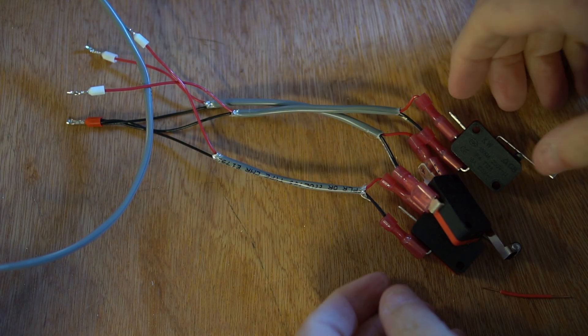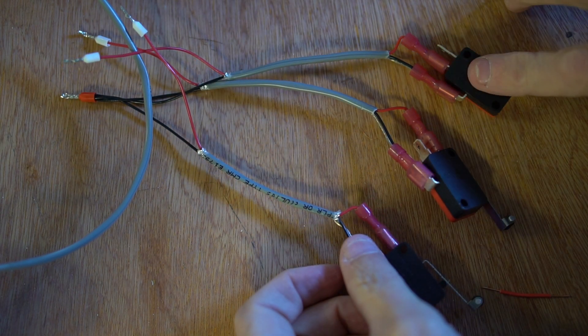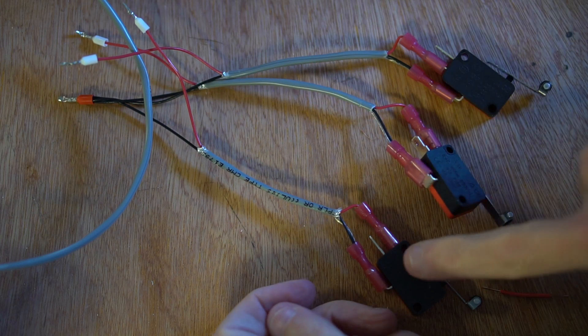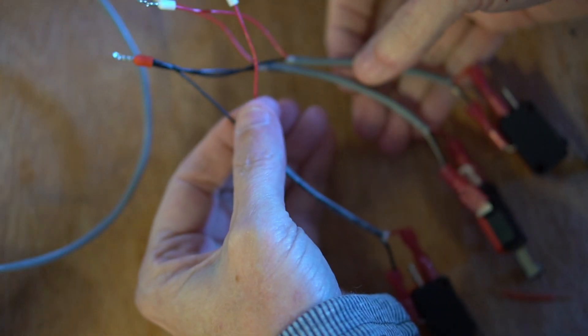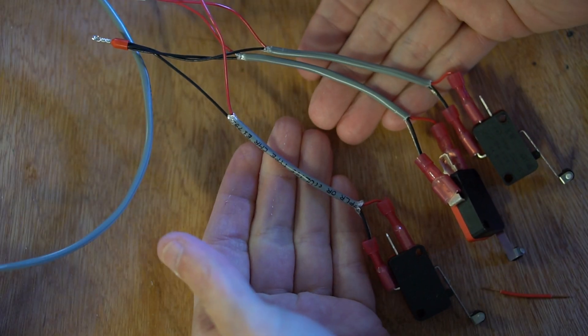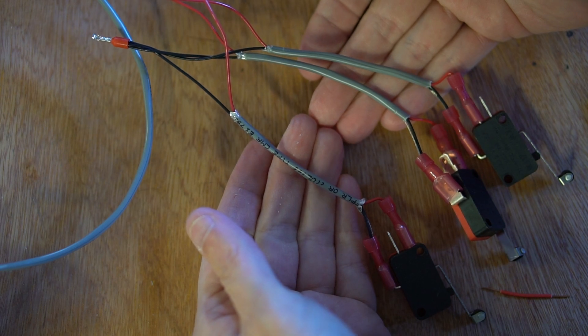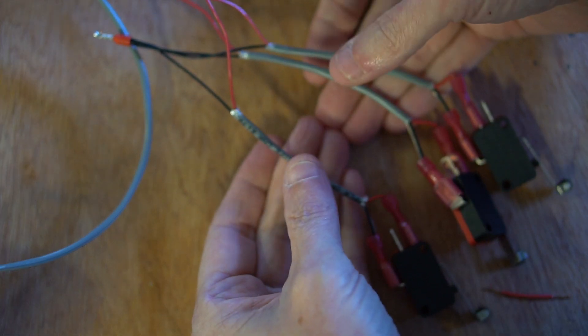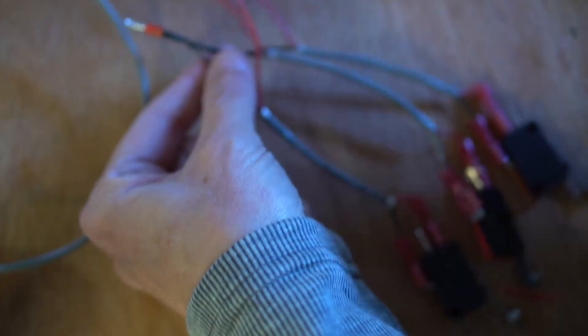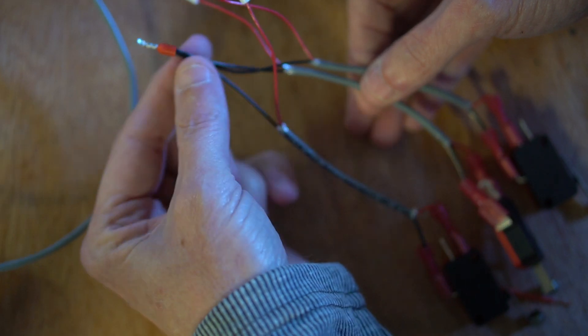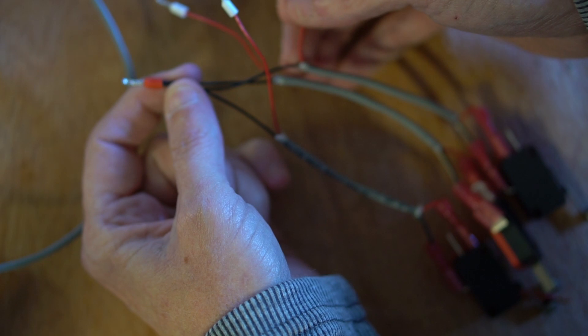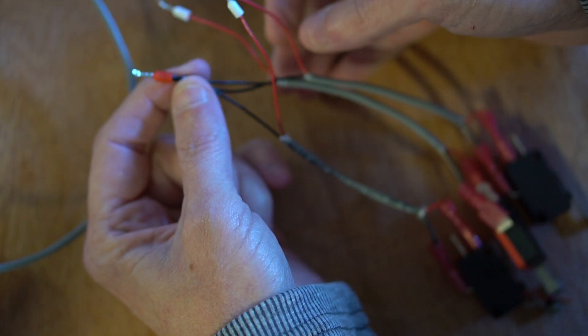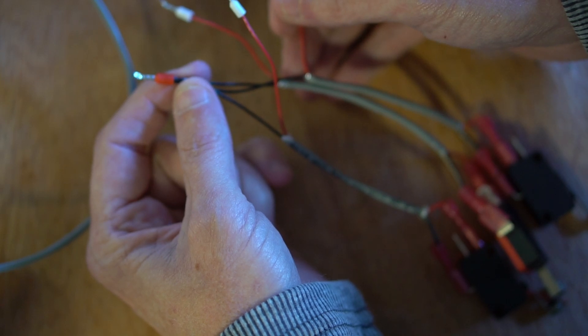I'm going to demonstrate connecting three limit switches. One for the home, one for the plus-plus, and one for the minus-minus. I'm using shielded cable, and there are two conductors in each cable. I'm using really short cables just for demonstration purposes. Of course, you'll want to use shielded cable because these are really susceptible to noise. And enough noise can stop the machine. I connected all the black conductors together along with the shield conductor, since these will be going to the ground terminal. I'm using wire ferrules to terminate the ends of these wires. I put a link in the description where you can get these wire ferrules and the tool to crimp them.